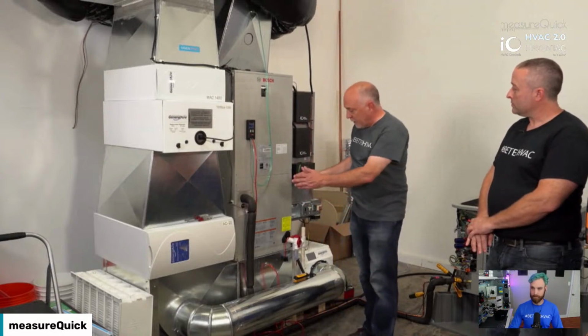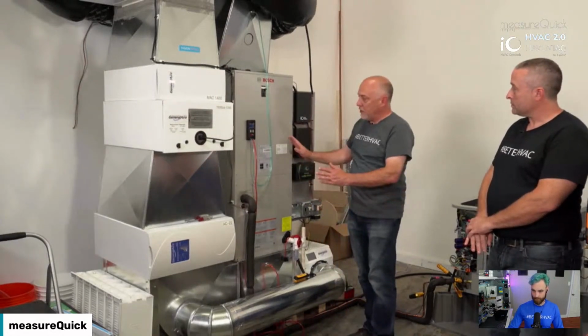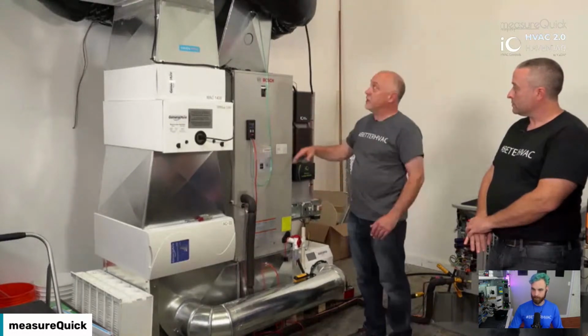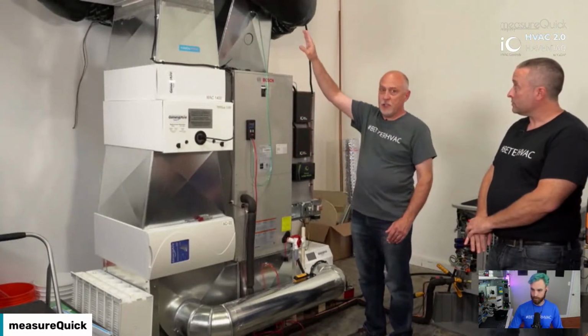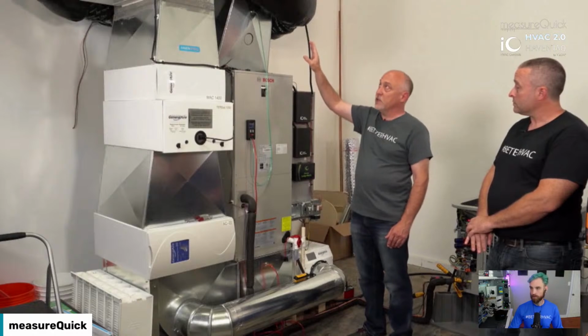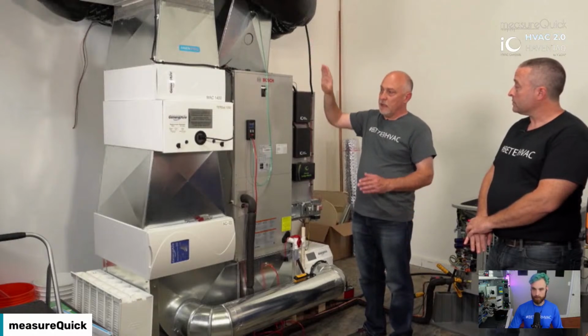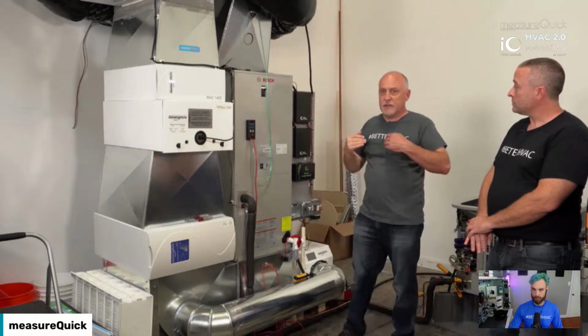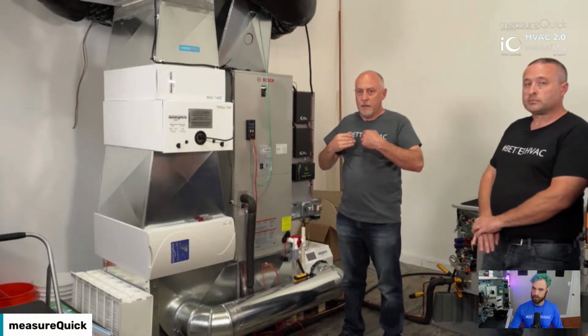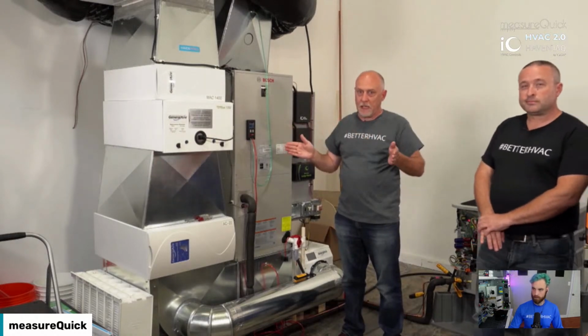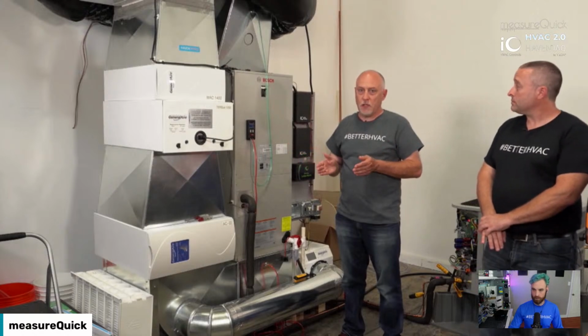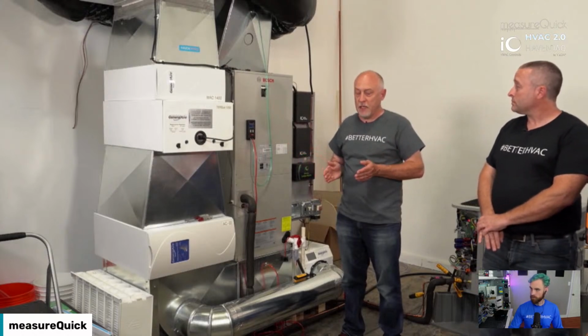This is all tied in with a Bosch heat pump, and the Bosch heat pump is running now. We're running about 0.2 of an inch of static, and we've got 2 different duct systems tied in with this. So we actually designed the duct system so we could move the air out of the space and then back around to the filters. We're working with what's called an entrainment model to try and get the air to move.